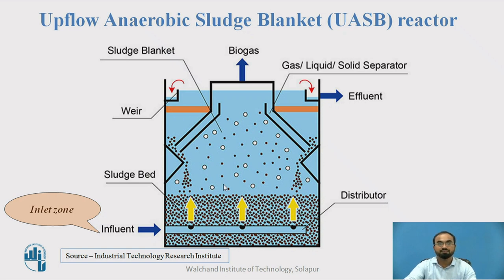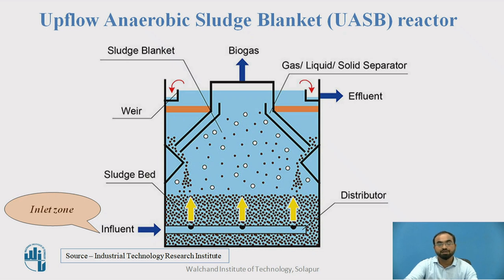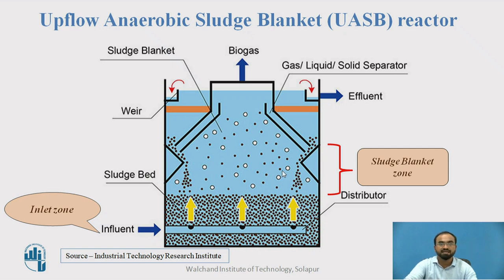As the water passes upward — upflow means the wastewater is flowing upward — the wastewater comes into contact with the microorganisms present in the middle part of the tank. The anaerobic microorganisms present in this tank attack the organic matter in the wastewater and it is automatically digested, forming two things: one is biogas, and another is biomass or sludge. Normally biomass is around 5% of the total organic matter, meaning 95% efficiency of UASB can be achieved. This middle area where digestion of organic matter takes place is known as the sludge blanket zone.